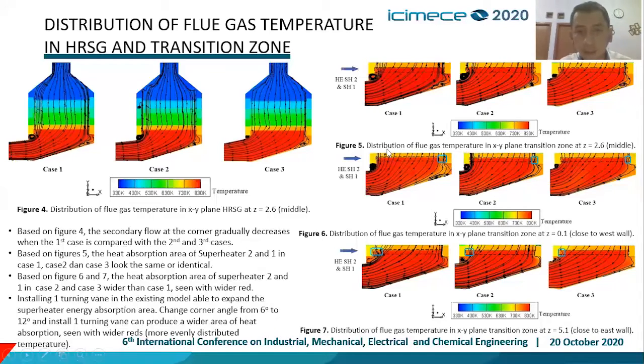look the same or identical, but in figures 6 and 7, in the west wall and close to the east wall, the heat absorption in case 2 and case 3 is wider than case 1, seen with the wider red. Installing one turning vane in the existing model is able to expand the superheater energy absorption area. Changing the corner angle from 6 to 12 degrees and installing a turning vane can produce a wider area of heat absorption.